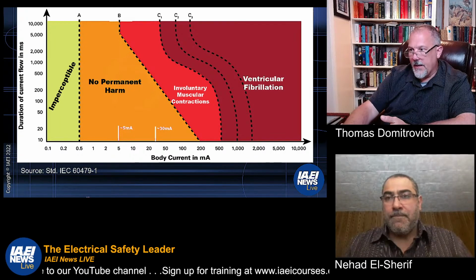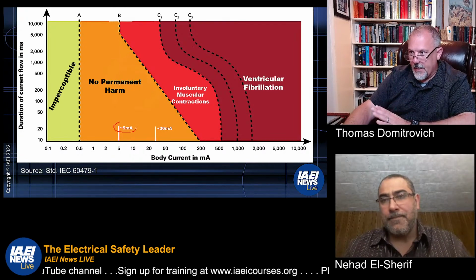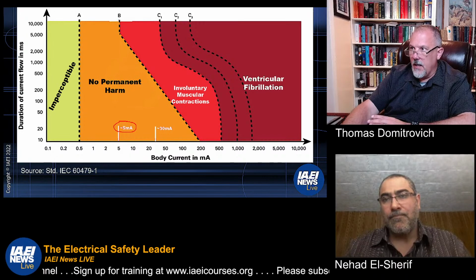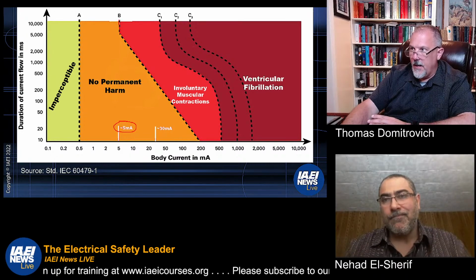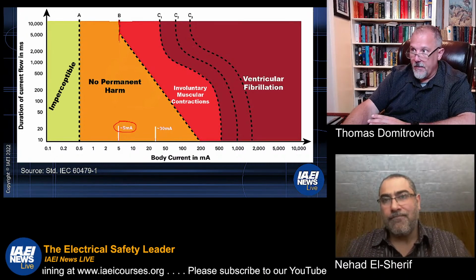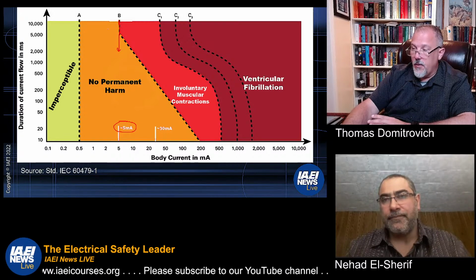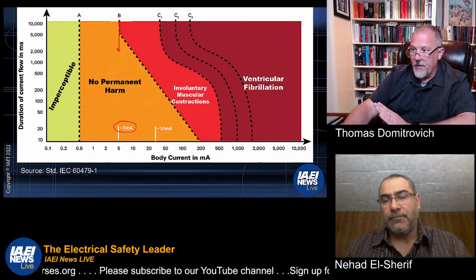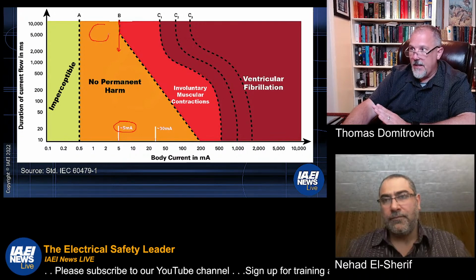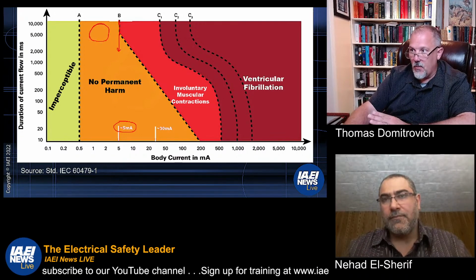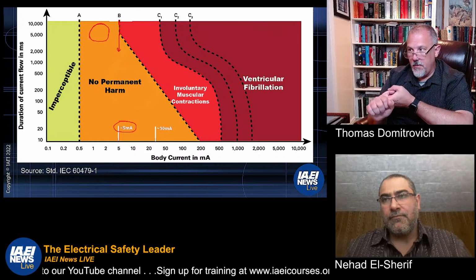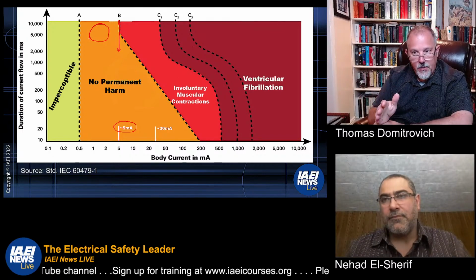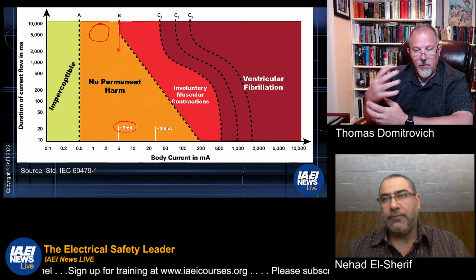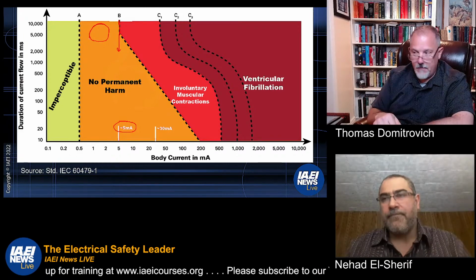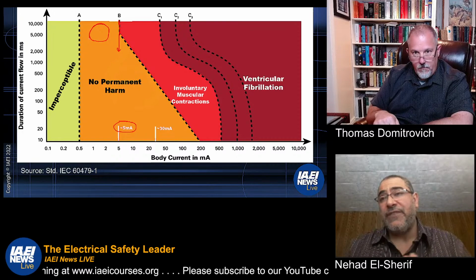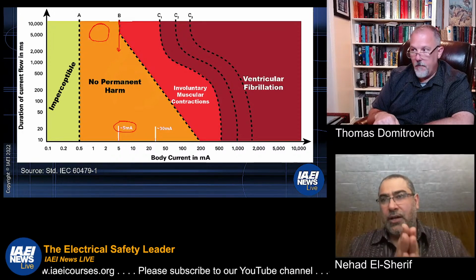So I can't help but recognize that the 5 milliamps lines up with this B line right up here, right? So what we're saying is that for currents less than 5 milliamps, you have no permanent harm. And is that your let go threshold? That's where you will be able to let go if you're less than 5 milliamps? For sure, and this is the Class A GFCI threshold, right?